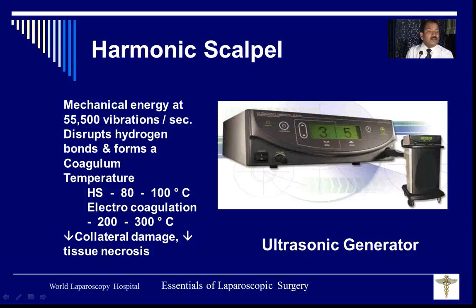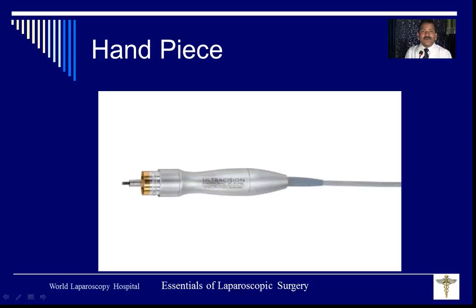So bring its transducer, the harmonic's. So what is there? It vibrates at 55,500 vibrations. This is a piezoelectric crystal inside. Take it fully, lift it up. The piezoelectric crystal is on this side, and it is just like the vaginal probe of an ultrasound. Isn't it? If you remove this cup, there is a screw, and on this screw you can attach anything you want, hook and the seal. Whatever you attach here, it will vibrate linearly. And you can attach a harmonic hook, harmonic knife, harmonic ace, harmonic shear, harmonic wave. There are many instruments which can be attached there.